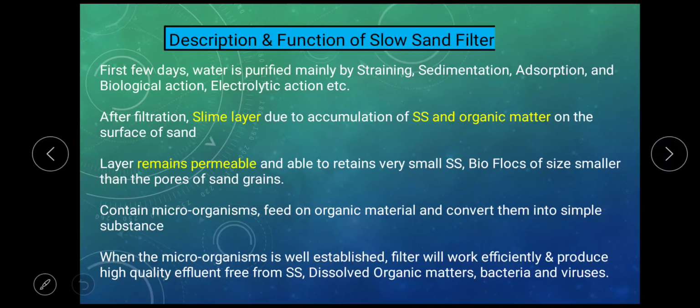Description and function of the slow sand filter. During the first few days, water is purified mainly by straining, sedimentation, adsorption, biological action and electrolytic action. After filtration, due to the accumulation of suspended solid organic matter and other biofloc, a slime layer is formed onto the surface of the sand. This slime layer is permeable and able to retain very fine suspended solid biofloc and other impurities whose size is even smaller than the pores of the sand grain.